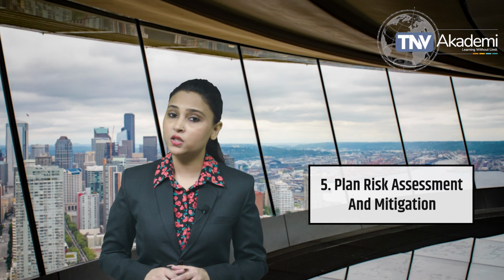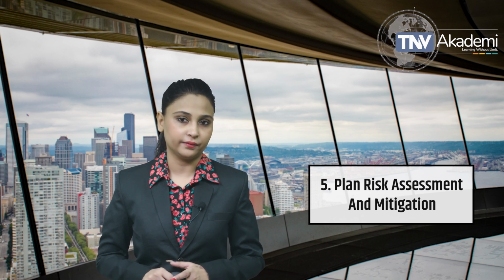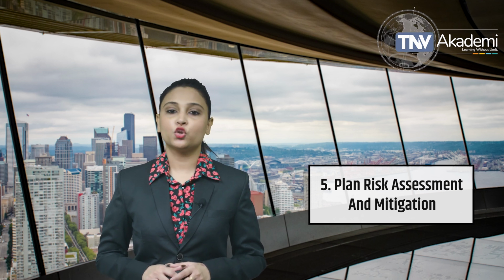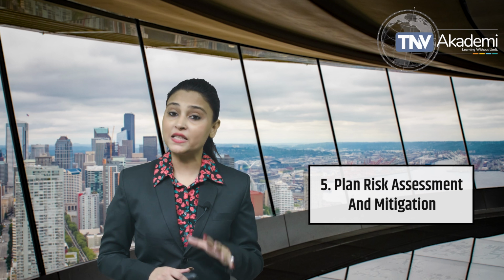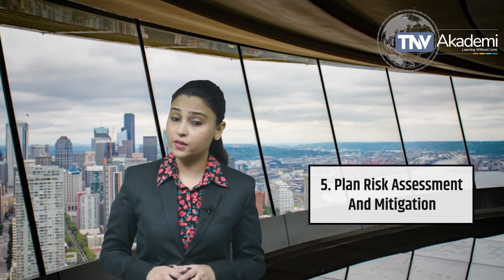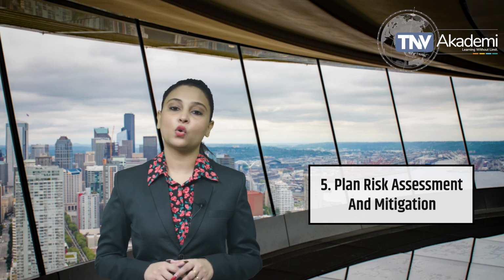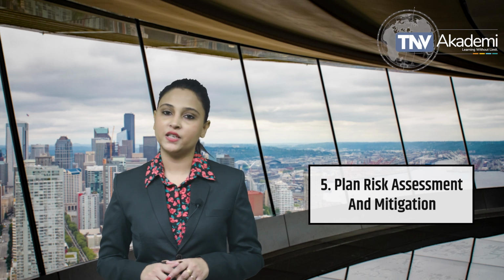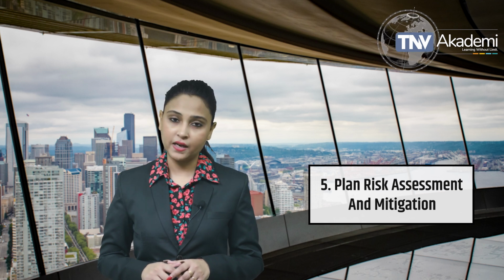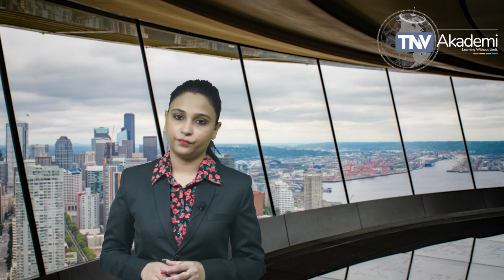Incorporate risk management into the biological evaluation plan. Identify ways to minimize or eliminate risks based on risk outcomes. If risks are identified, risk controls like material changes or additional testing should be included in the plan to ensure that any potential adverse effects are mitigated.